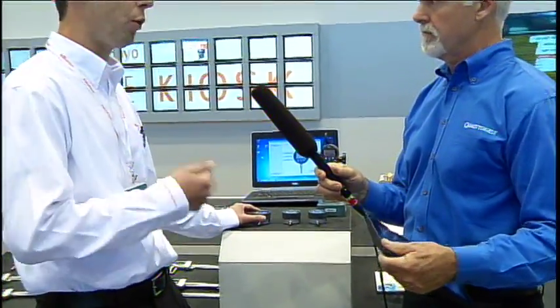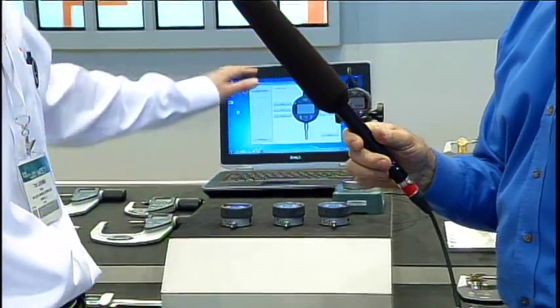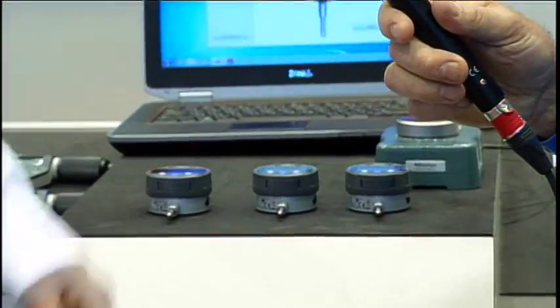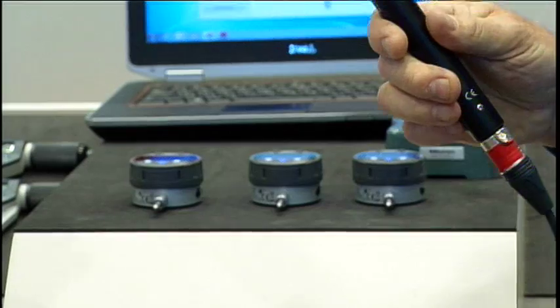The biggest advancement from this line of indicators from our past is we now have software available, so if you don't want to go through the buttons, you can program right on the software, and you can lock out your users from messing with the numbers. So if you went through the trouble of figuring out the coefficients to type into the calculation indicator, you don't want your guys going in there and zeroing it out. This way we can lock it out on the computer side and there's no way for them to change it. Oh, okay, that's pretty nice.